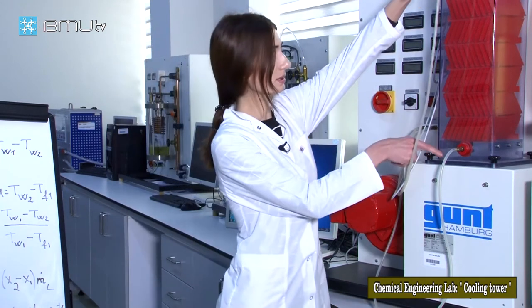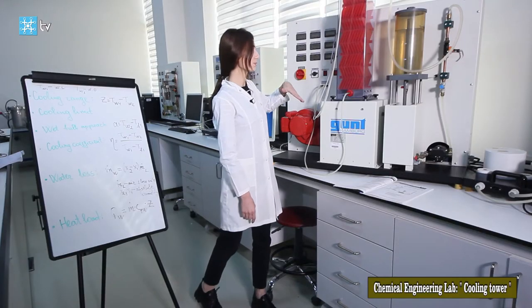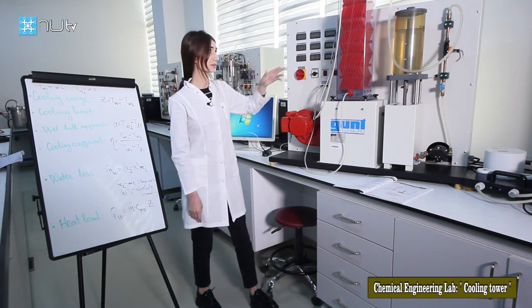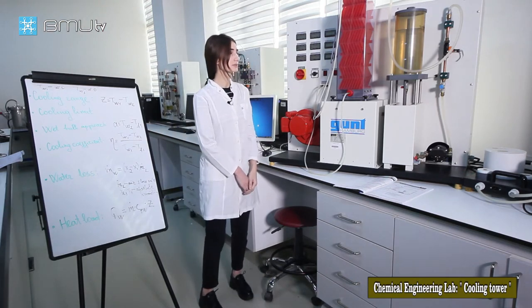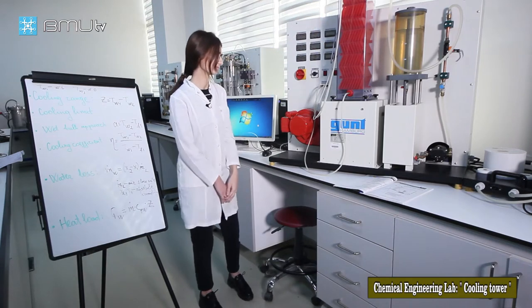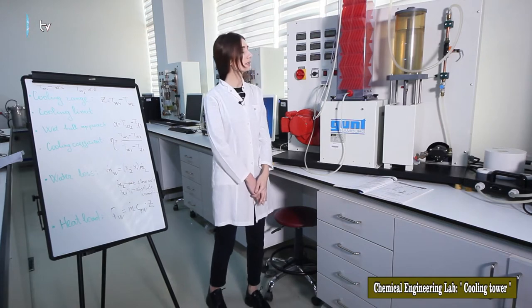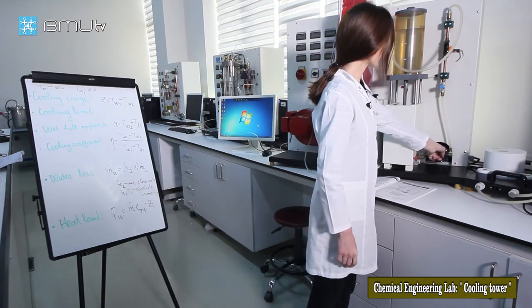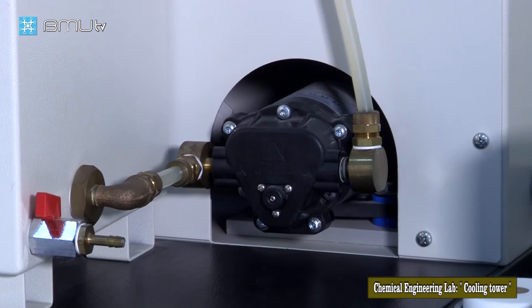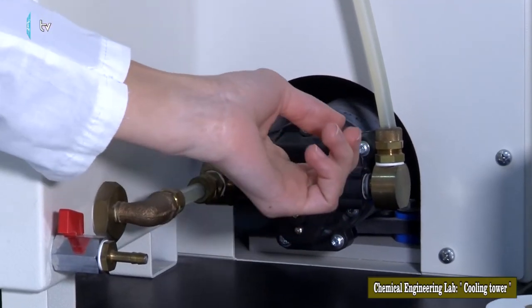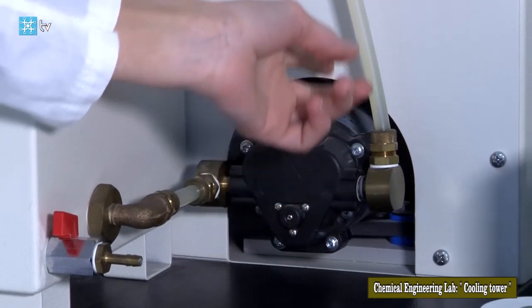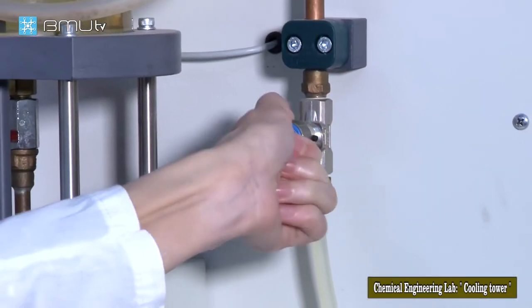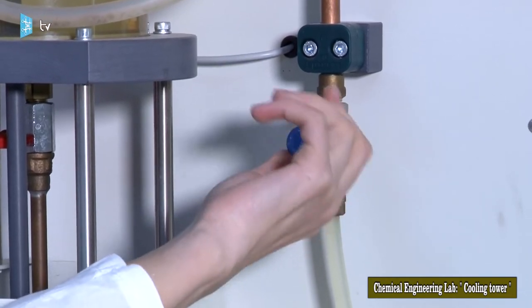The packing density is the ratio between the total surface area of all the slats and the volume of the cooling column. Next, let's talk about the pump. The water to be cooled is pumped through the circuit by a centrifugal pump, and the flow rate of water can be regulated by a regulator valve. We can increase or decrease the volumetric flow rate of water by adjusting this knob.